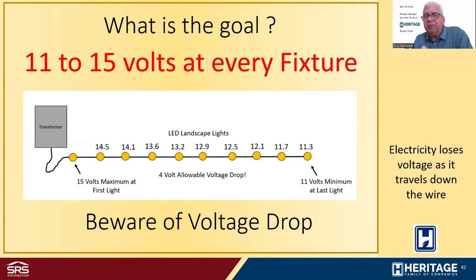Now, there's a problem that could be created if you don't do this. Let's say I had more than 15 volts at my fixtures. Well, many of the LED circuit boards that drive these fixtures are not made to operate at over 15 volts. In the same way, let's say I had less than 11 volts on my fixtures. Well, some LED fixtures are not designed to operate at less than 11 volts. So if you have less than 11 volts or more than 15, there's certainly a possibility that that LED is going to fail because it wasn't designed and engineered to operate outside that voltage range. So just know that LEDs, no matter what type you use in the marketplace today, if they're low voltage LEDs for professional outdoor lighting, they're all going to work from 11 to 15 volts. So that's where we need to make sure that they operate at 11 to 15 volts.